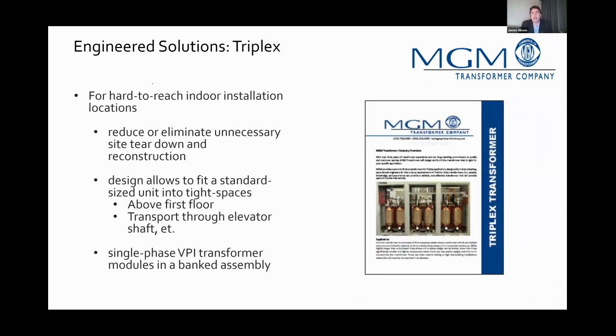So if you have an application, whether it's a high rise residential building or a business park, and you need to get a large 3-phase transformer up onto the 10th floor through an elevator shaft, triplex units are made for those applications. They come in single units, single phase modules, that once they're on site, are assembled into the final transformer design.